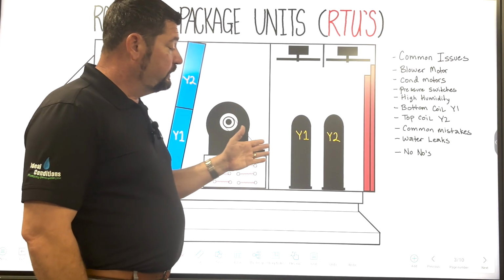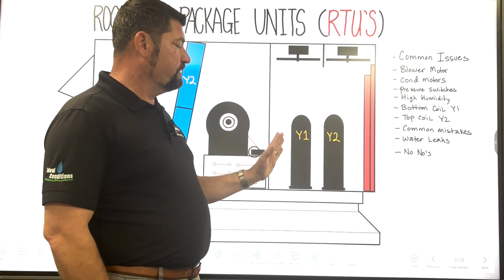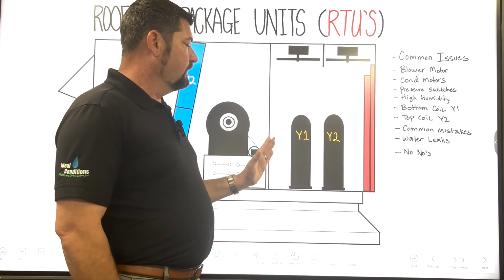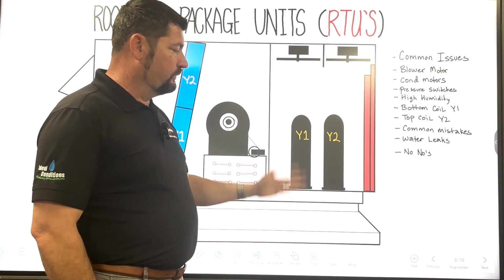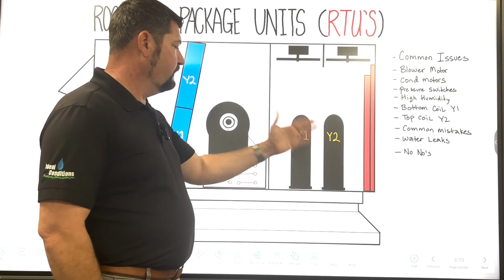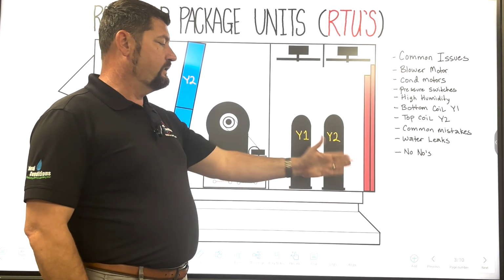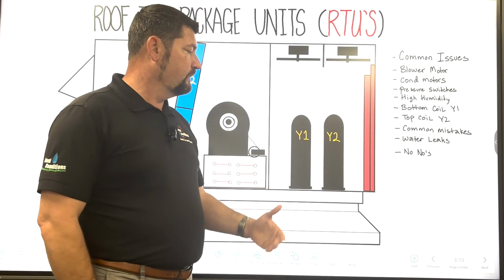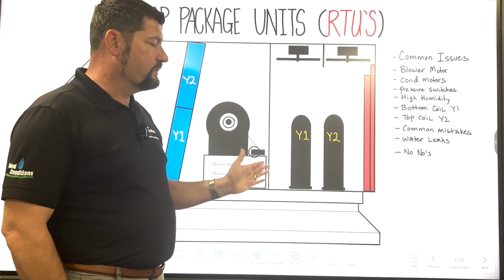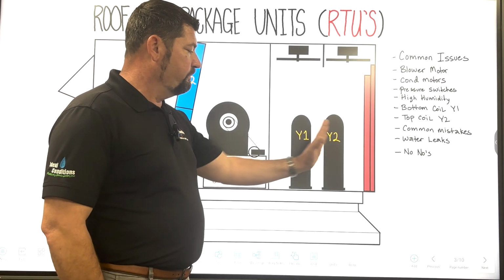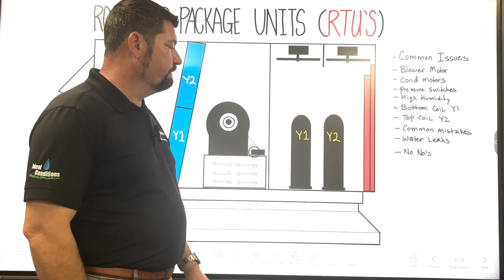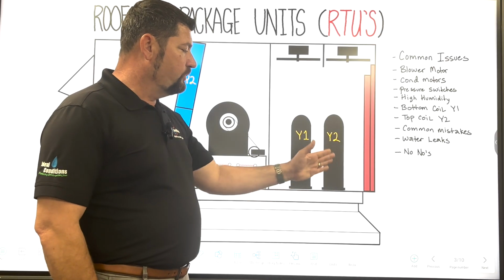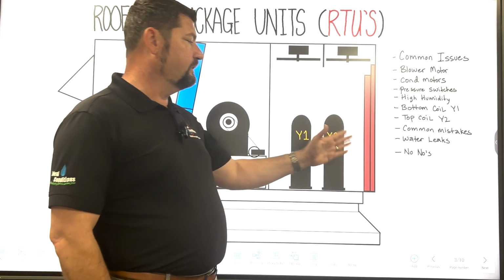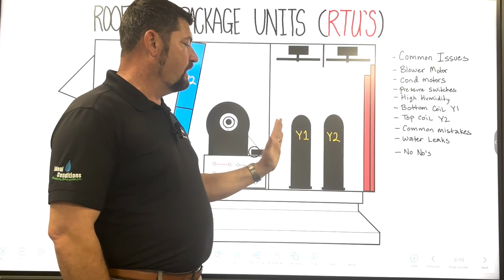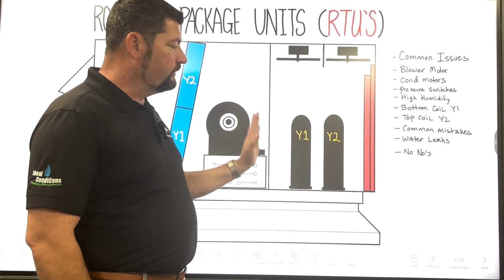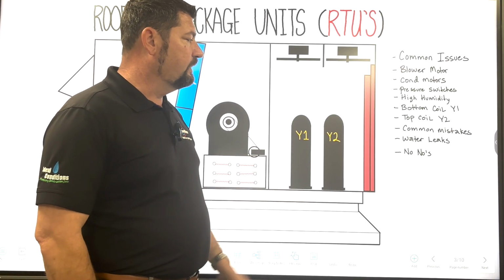So when you look at Y1 and Y2, they're supposed to be coming on independently. Y1 is your first stage, Y2 is your second stage. So in the event that we need Y2 to come on, just like in residential equipment, that commercial rooftop unit's designed the same way. It's to be in addition to Y1, right? Nice thing about having two compressors is also that there's a little bit of redundancy. So if one goes down, you can have the other one. However, it doesn't always work out that way when it comes to humidity, which we'll go over in a second.